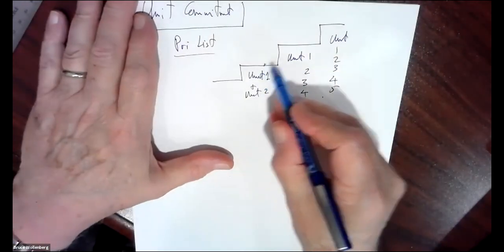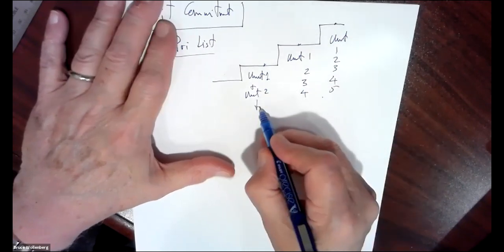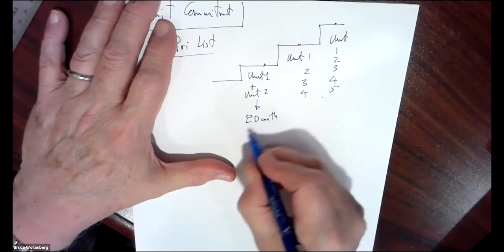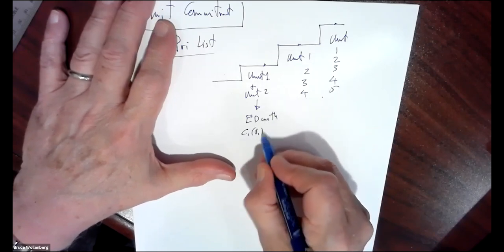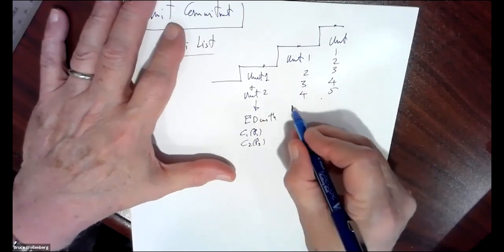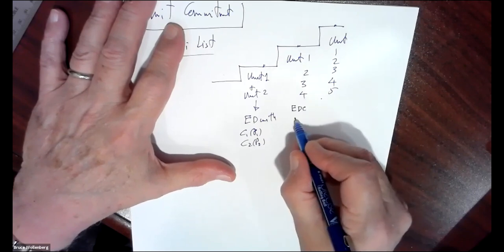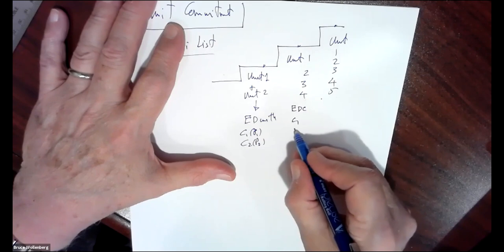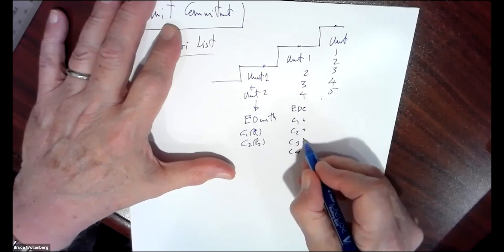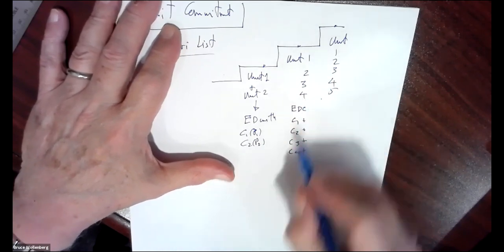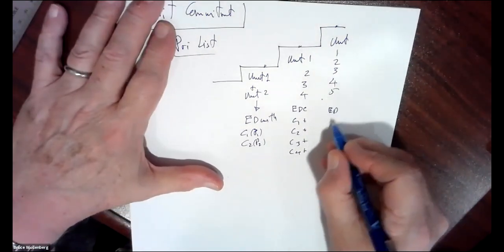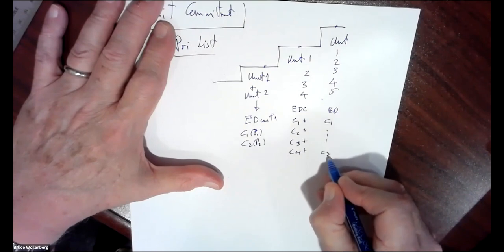Well, what I need to know for each of these values here is I need to run an economic dispatch with C1 of P1, C2 of P2, just the one and two. Here I have to do an economic dispatch with C1, and then C2, C3, C4. So I have four generators because I've committed four of them in here. And similarly here, I would have an ED with C1 to C5.